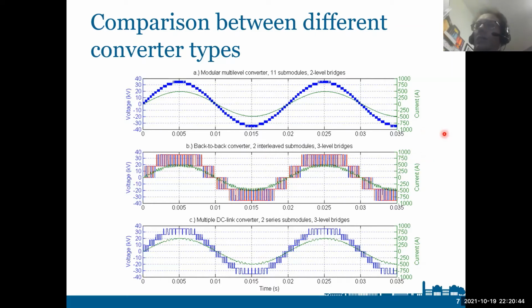So there are obviously advantages and disadvantages for the various topologies, and at least the first two have been used quite widely for 16 Hz and 50 Hz railway, while the MMC has been used mainly for 16 Hz railway, due to the advantage of having a conversion in a single step. For a 50 Hz railway, the advantage is slightly reduced because of the need of this double-stage conversion.